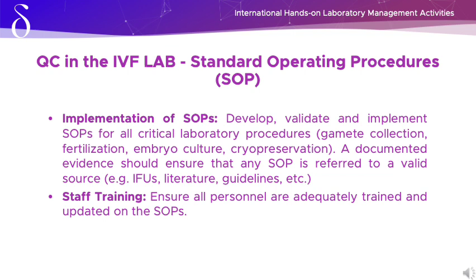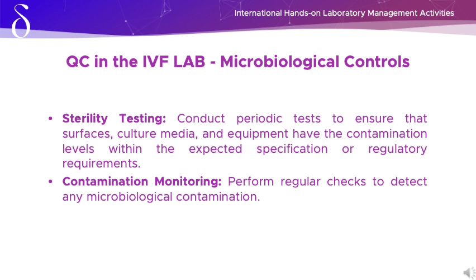Also, microbiological control must be done in the laboratory, so we have to conduct periodic tests to ensure that all the surfaces, the culture media and the equipment have a specified contamination level, and that these contamination levels are within the expected specification or within the regulatory requirements. For example, as I was saying before, in the rooms of the laboratory we need to stick to grade D, good manufacturing practices Annex 1 if the laboratory is in the European Community, and under the workstation the quality of the air and the microbiological contamination must be according to grade A GMP Annex 1. And all this activity must be done under regular checks to detect and to correct any microbiological contamination that is above the expected levels.